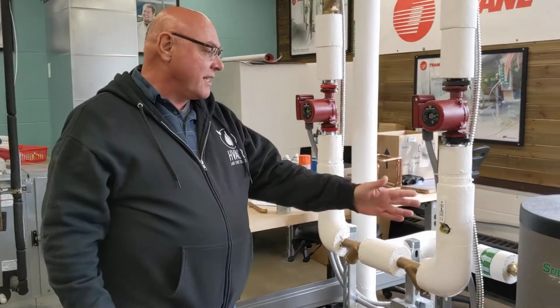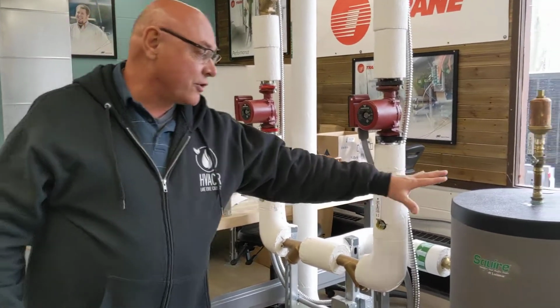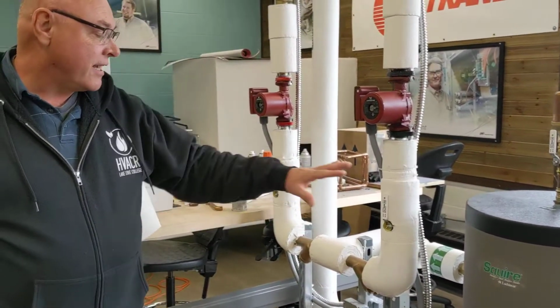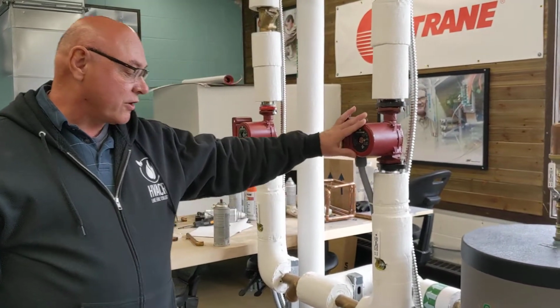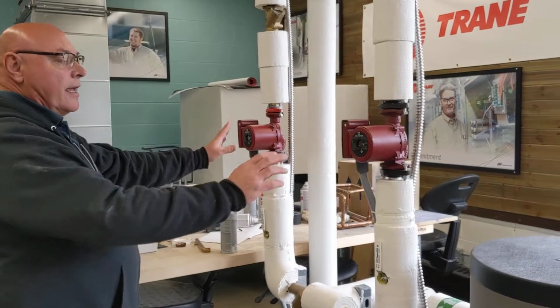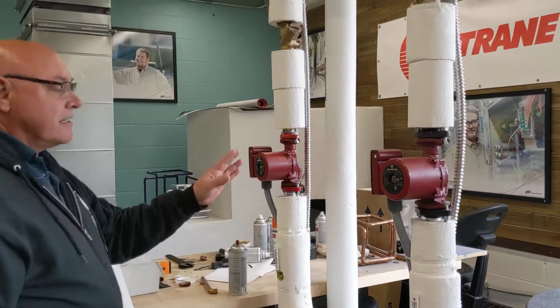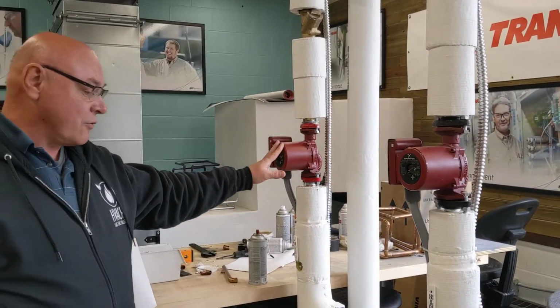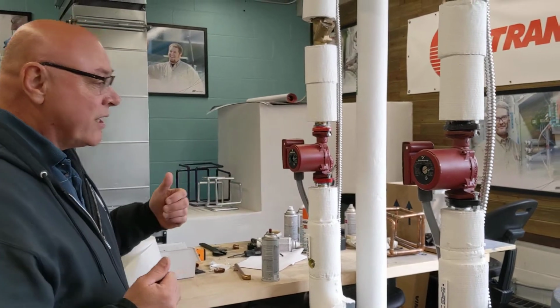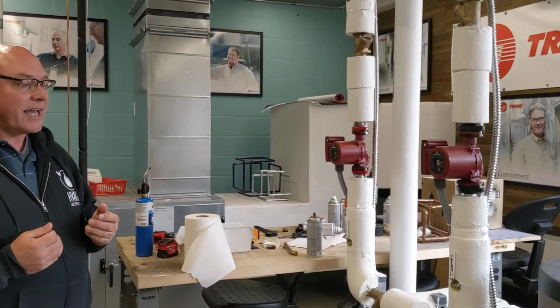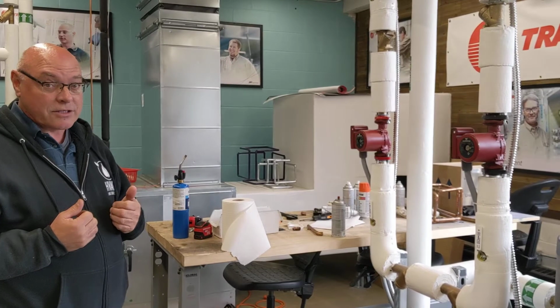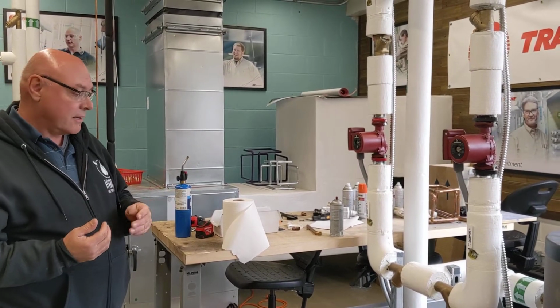So now we're going to explain the second half, after our heat exchanger. Our heat exchanger is actually making this water warm, and here we have two pumps. They're redundant, so if one fails, we have another one.